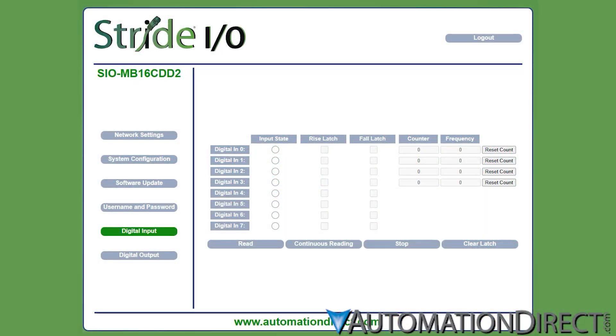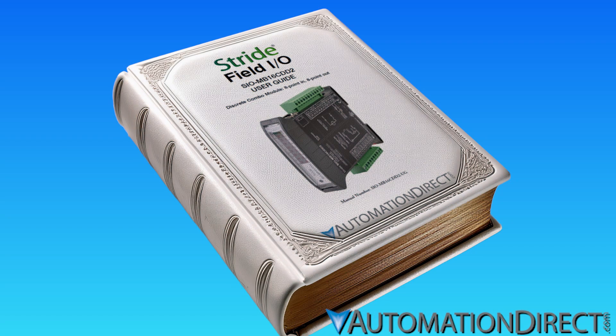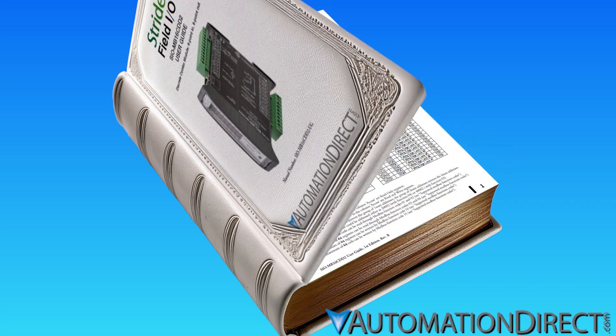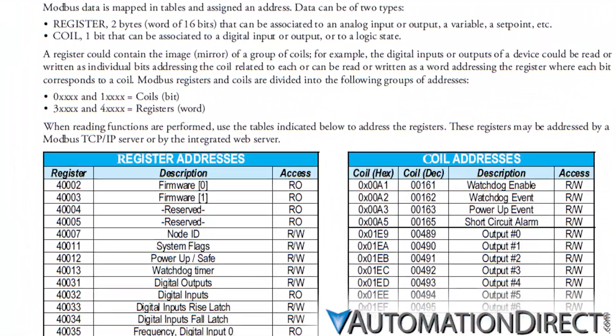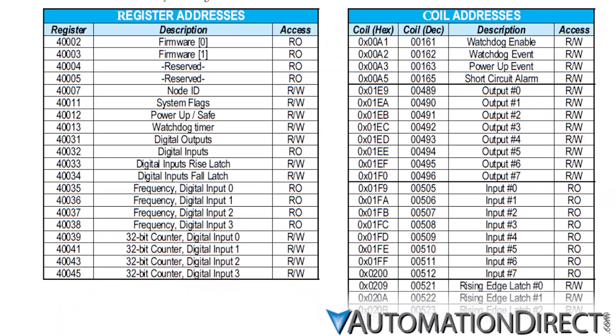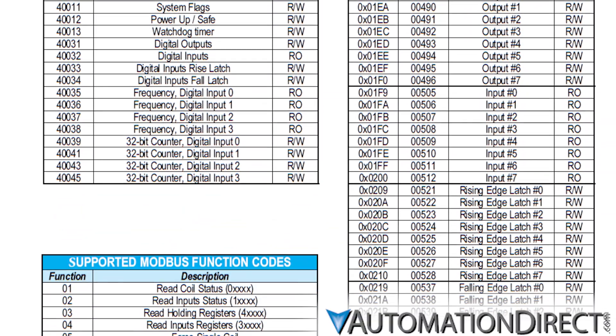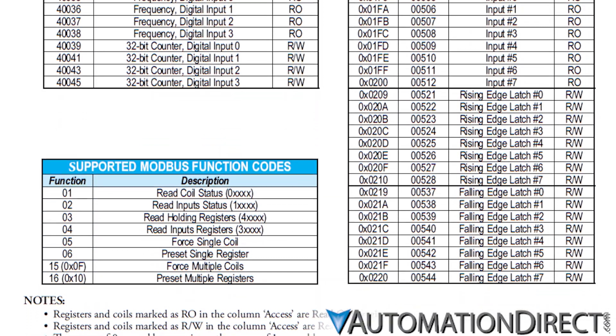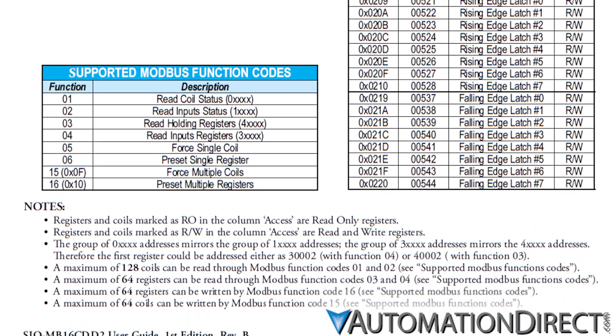You can monitor the state of the I/O points and various system data. The module's user manual provides full details. Importantly, the manual also contains the device's Modbus map, providing the offsets that will allow your controller to access all the I/O data the Stride module is collecting and to control its outputs.